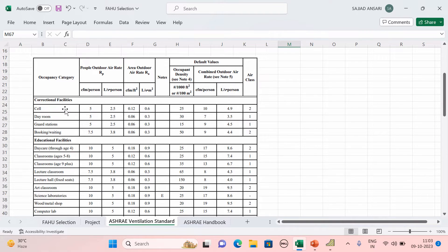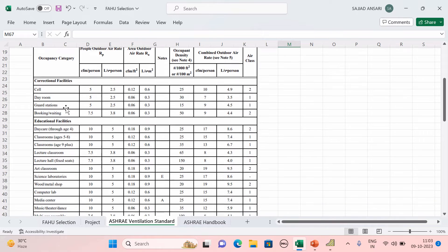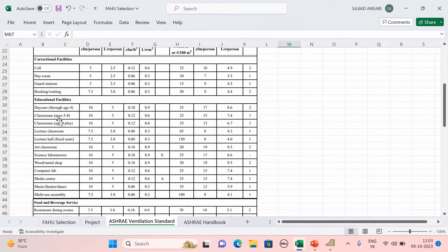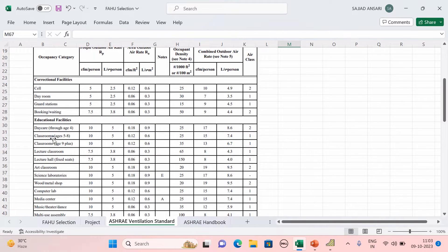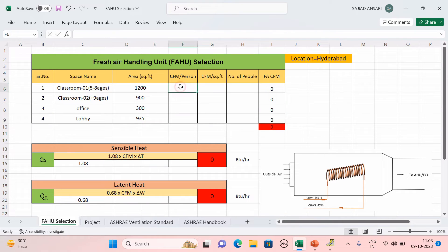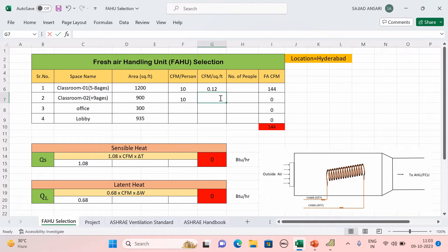We are calculating CFM per person and CFM per square feet for classrooms. For ages 5–8, CFM per person is 10 and CFM per square feet is 0.12. For ages 9+, CFM per person is also 10 and CFM per square feet is 0.12. Write down those details.